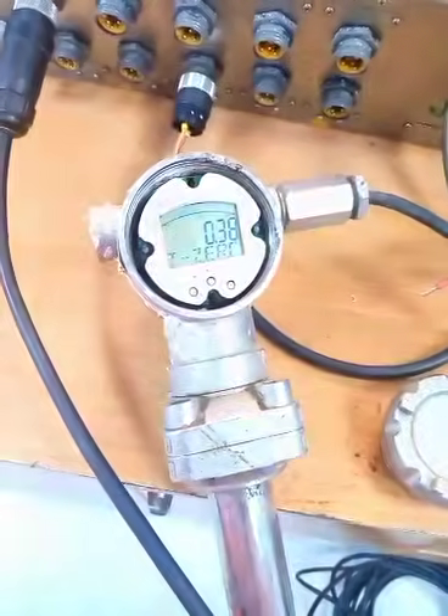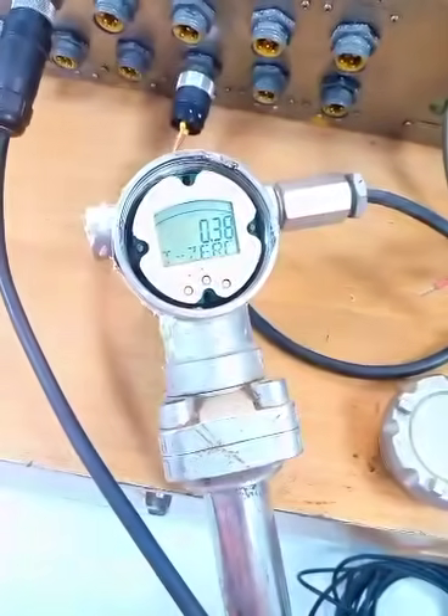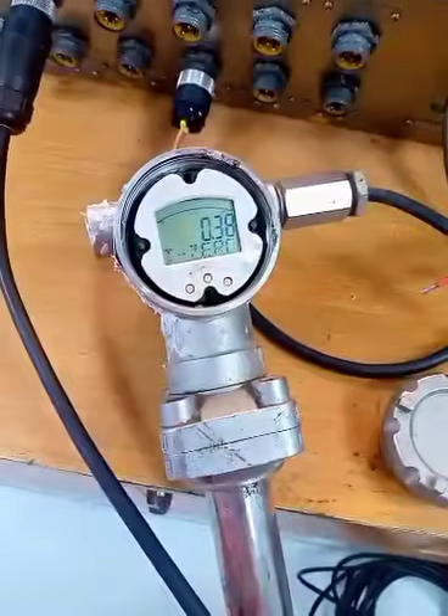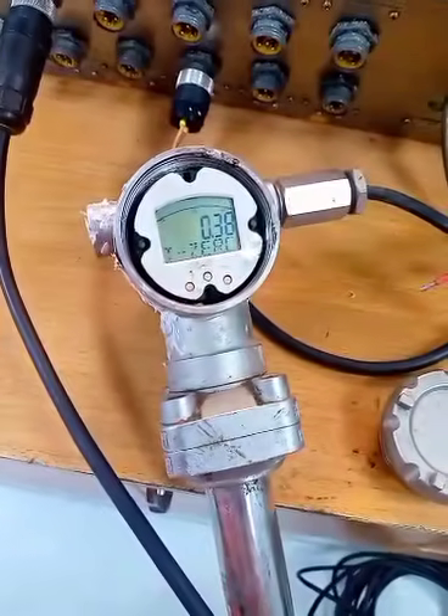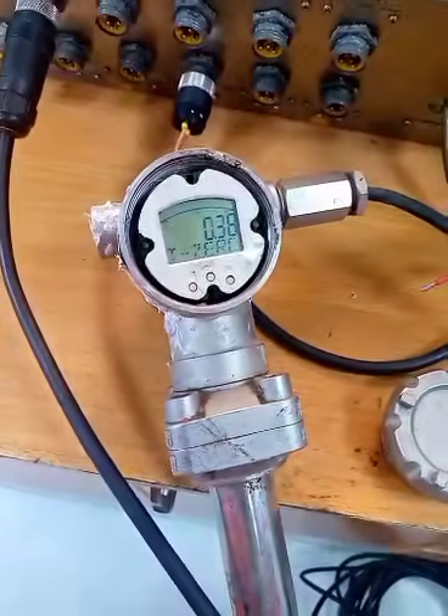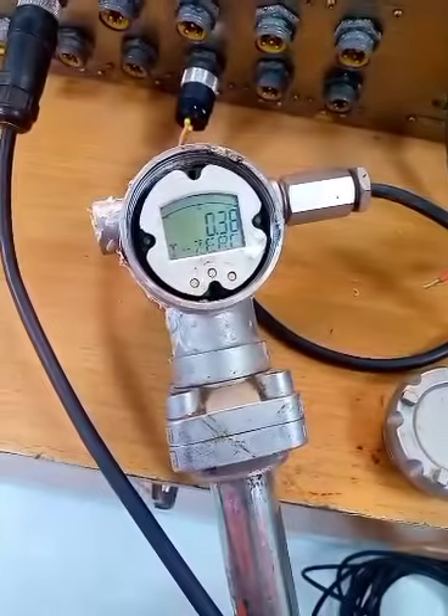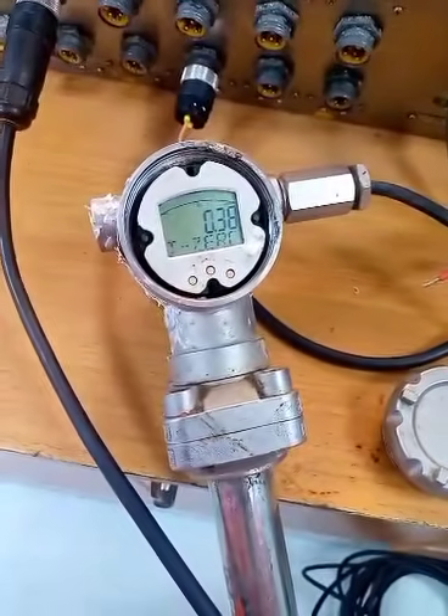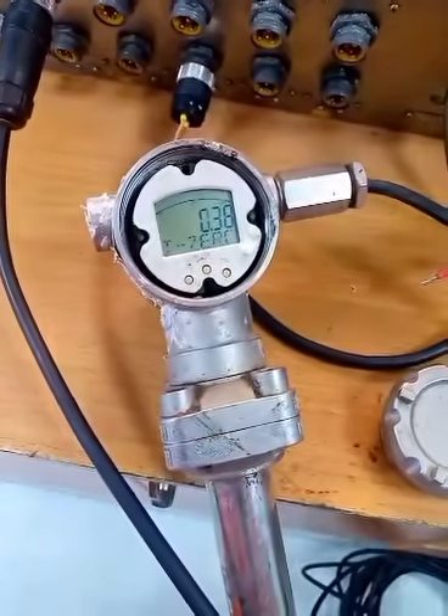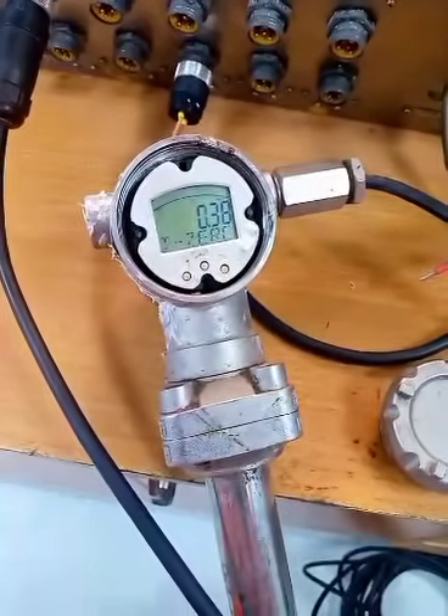Then from there you have gotten both the low and the high calibration. You can now extrapolate to 20 milliamps and calculate that mathematically to get the corresponding value of 20 milliamps. And that's all. Thank you very much.